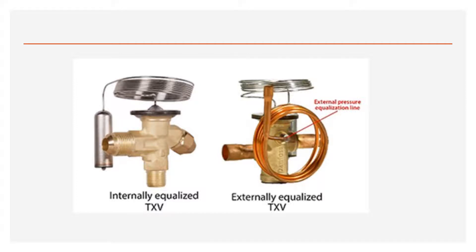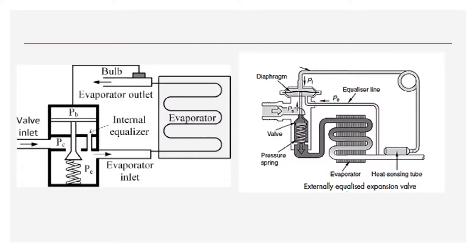An internally equalized TXV uses evaporator inlet pressure to create a closing force on the valve. An externally equalized TXV uses the evaporator outlet pressure, thereby compensating for any pressure drop through the evaporator.